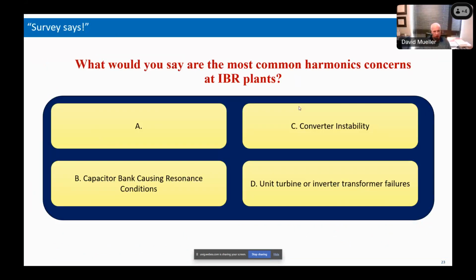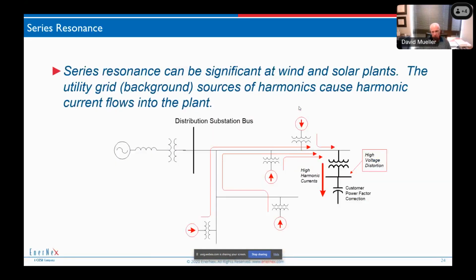Capacitor banks in our IBR plants causing resonance conditions. This is probably one of the most common ones. It's also very important because many plants use capacitors as an effective way to offset the reactive power losses in the transformer and the collection system to meet the reactive power requirements. But that capacitor bank introduces resonance considerations, and that resonance can cause a problem inside the plant, and or it can cause a problem on the transmission system at the point of interconnection, where it magnifies harmonic current levels.